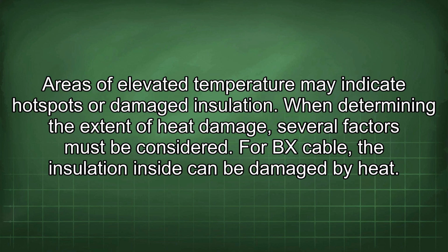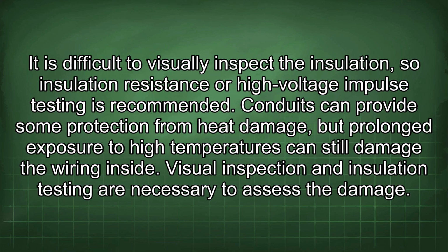When determining the extent of heat damage, several factors must be considered. For BX cable, the insulation inside can be damaged by heat. It is difficult to visually inspect the insulation, so insulation resistance or high voltage impulse testing is recommended.